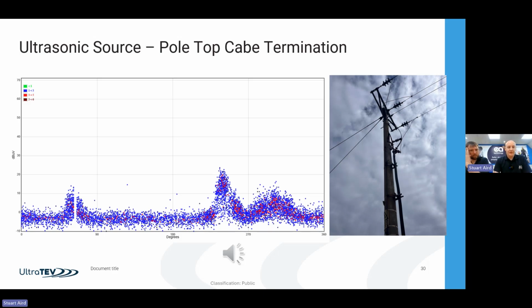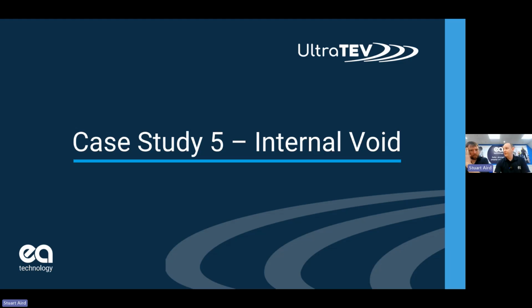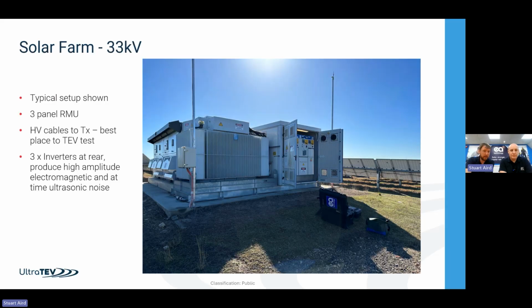Okay, next one is back to another internal void example for you. So another internal void example, and again this is another high noise example - unfortunately more and more of the sites we go to have got high noise. Quite often setups like this - and this is actually a case study, you can see from the sunny skies we should be thanking our colleagues in Australia for. Unfortunately didn't quite get that weather here, but they've got basically three inverters right next to a ring main unit there. So from an electrical noise point of view this is quite high and relatively challenging to look for PD in, especially where everything's energized.